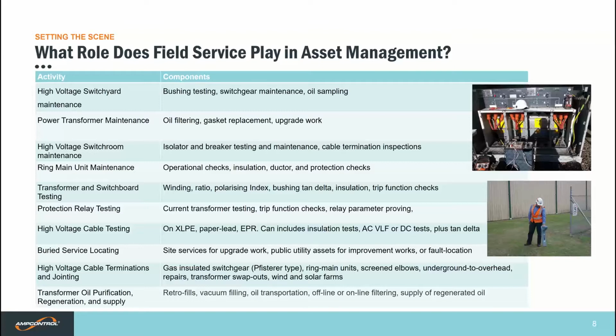With high voltage cable testing, these can be on XLPE cables or your good old paper leads or your newer EPR type, as well as rubber cables used extensively through metalliferous mining situations. Can also include insulation test, being AC VLF, which are pretty common nowadays, or DC test plus tan delta testing. Buried services locator is something that we occasionally do. Site services for upgrade work, possibly for public utilities, if they want to do improvement work, or doing fault location work. High voltage cable terminations and jointing, gas insulated switchgear using your Pfisterer type plug-ins, ring main units, screened elbows, underground to overhead cables, repairs on cables, swap out, and lately a lot of wind and solar farm work.